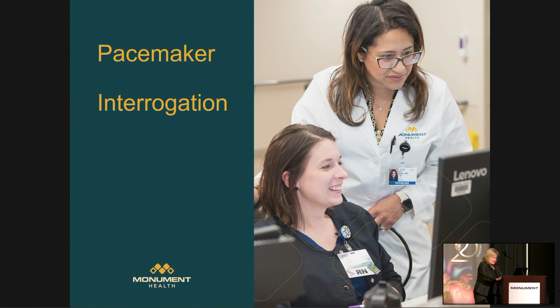So this is a typical printout from a pacemaker interrogation, and this is the lady at explant time. Some of them say ERT, elective replacement time. Hers says explant time. The little gas gauge on the right side would be all the way to the right at the 3 o'clock position when it's new, and then as the battery ages, there's a little dial like a clock, and it reaches a spot called 1 year remaining, and then explant. When it hits 1 year remaining, they start doing more frequent checks to track the battery life closer, so they catch it when it hits elective replacement. Hers reached elective replacement on May 8th, 2023, and was replaced.